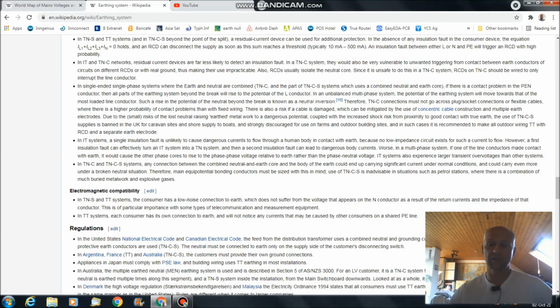Because even if it has a fault, you cannot make a fault current flow basically over the earth, and that's very safe. However, a first insulation fault can effectively turn an IT system into a TN system, and then a second insulation fault can lead to dangerous body currents.